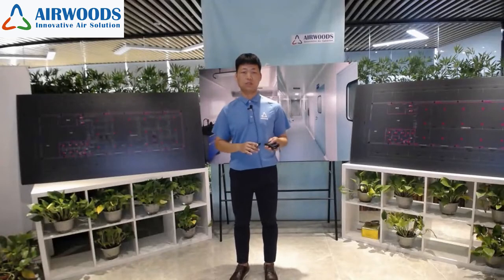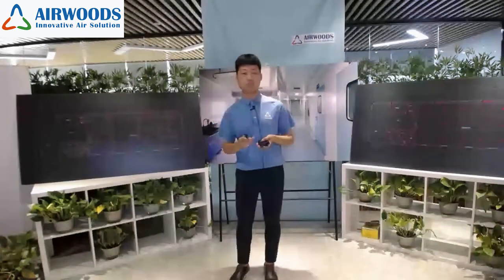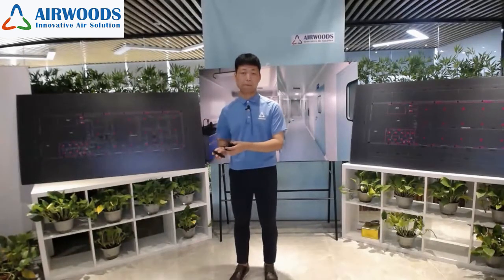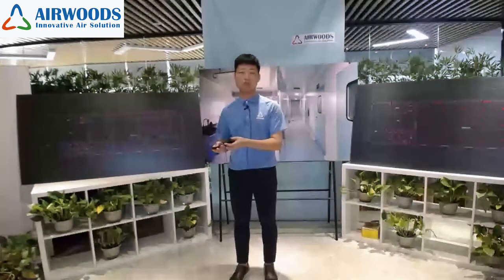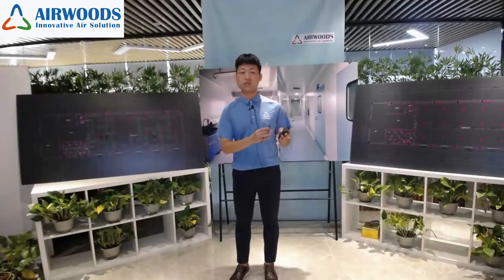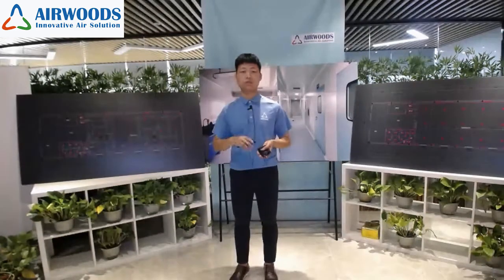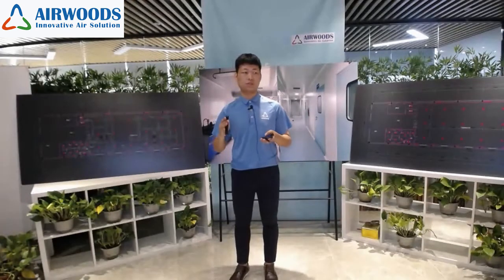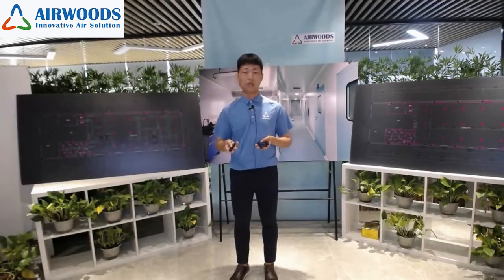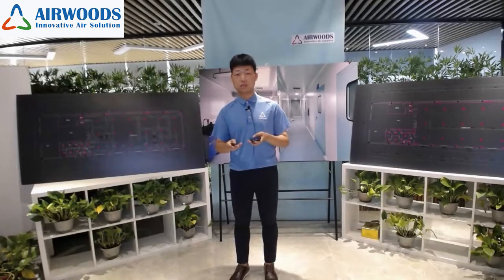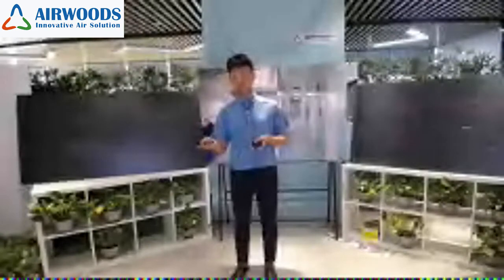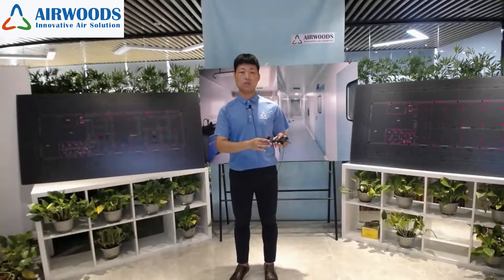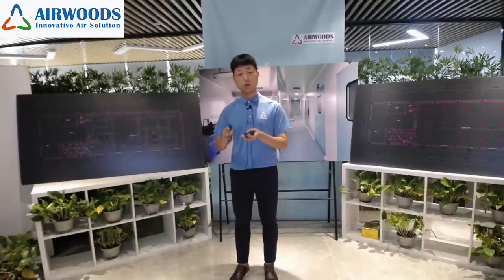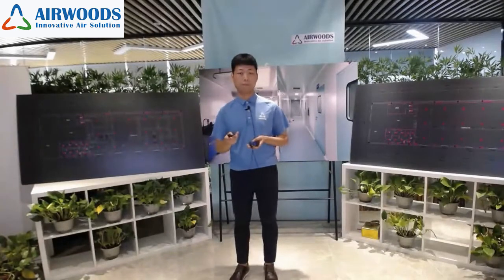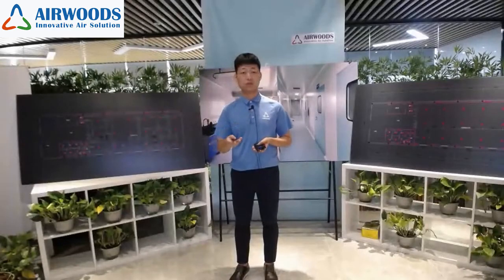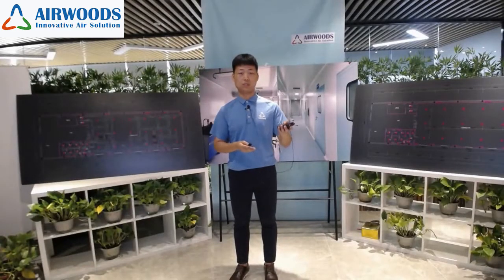The next part is about the floor. For the cleanroom, there are two options: the PVC floor or the epoxy floor. When we suggest PVC floor and when we suggest epoxy floor depends on the cleanroom area. If the cleanroom is larger than 500 square meters, we usually suggest using epoxy floor. If the area is less than 500 square meters, you had better use the PVC floor. We suggest this based on economic reasons, to save your money. And we will show the real pictures of the PVC floor on the slides. Okay.